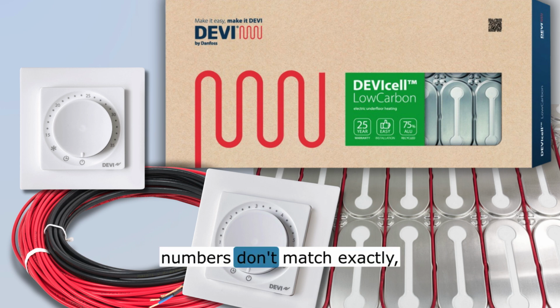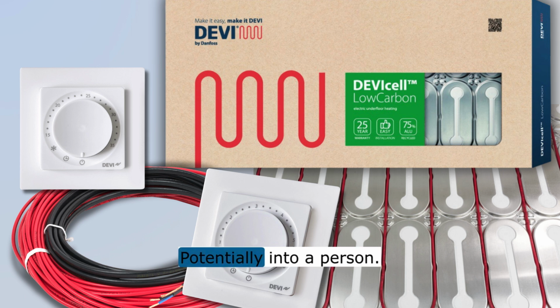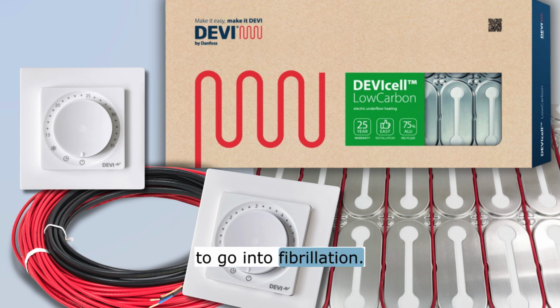Okay. And if those two numbers don't match exactly, it means electricity is leaking somewhere it shouldn't be, potentially into a person. Wow. Yeah, and that 30 milliamp limit is standard because that is the threshold of current that can cause a human heart to go into fibrillation. It shuts the system down instantly. Okay, that makes perfect sense. But there was an asterisk in the manual. It said you could go up to 300 milliamps in certain industrial setups because of something called capacitive leakage. What does that actually mean?